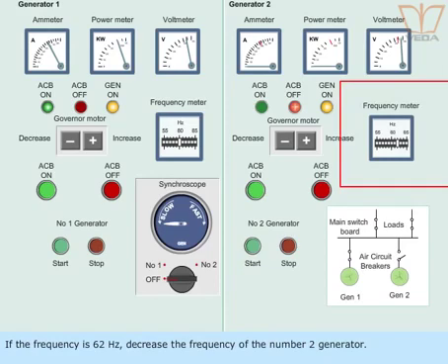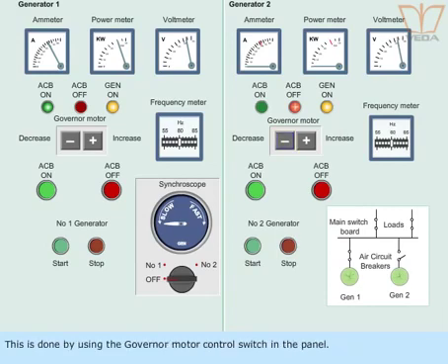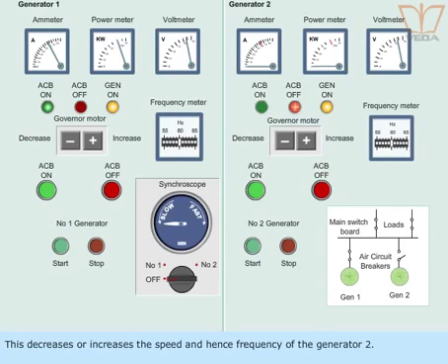If the frequency is 62 Hz, decrease the frequency of the number 2 generator. This is done by using the governor motor control switch in the panel. This decreases or increases the speed and hence the frequency of generator 2.